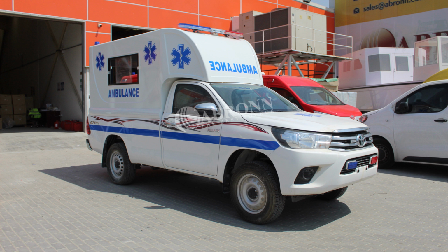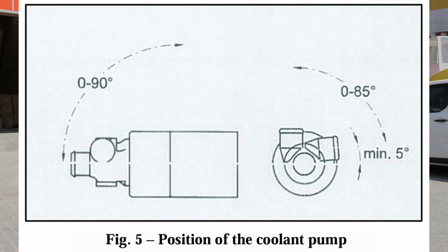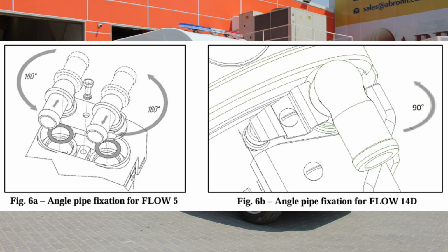Installation of the coolant pump. The coolant pump must be installed in the cooling circuit upstream of the liquid heater. The coolant pump should be installed below the level of the expansion tank, radiator, and heater. The direction in which the coolant flows in the pump must be the same as in the cooling system of the vehicle or vessel. The installation position of the coolant pump must not cause an airlock inside the pump. See the permissible installation positions in Figure 5.